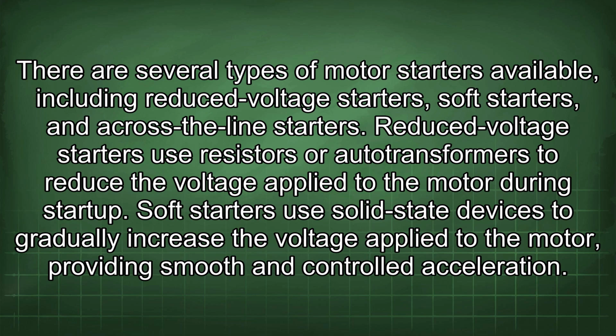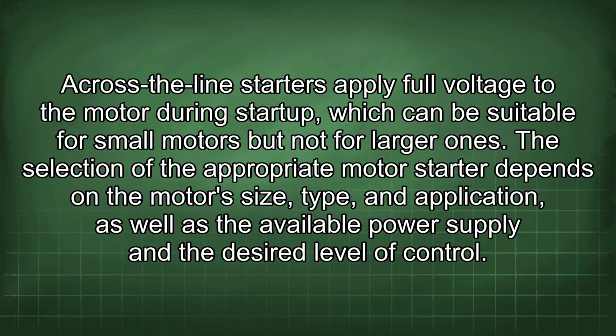There are several types of motor starters available, including reduced voltage starters, soft starters, and across-the-line starters. Reduced voltage starters use resistors or auto transformers to reduce the voltage applied to the motor during startup. Soft starters use solid-state devices to gradually increase the voltage applied to the motor, providing smooth and controlled acceleration. Across-the-line starters apply full voltage to the motor during startup, which can be suitable for small motors but not for larger ones. The selection of the appropriate motor starter depends on the motor's size, type, and application, as well as the available power supply and a desired level of control.